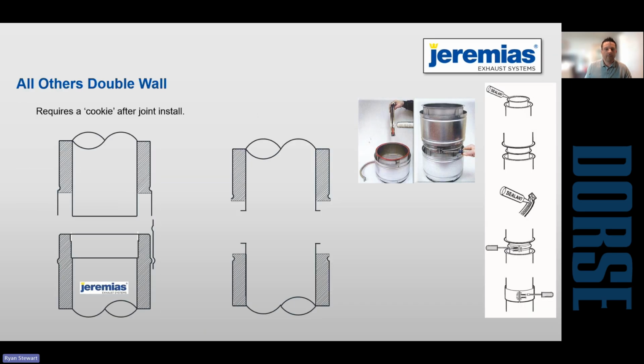What's unique about them compared to others, and they still build this as well, is there's a flange type product where you put a high temp sealant between the flanges, and then basically once you get that done, you put a clamp around the outside and a layer of insulation. Jeremias is the only one that offers a slip connection where the caulking goes on the outside of the duct. It slips in there and it's complete. So you don't have the extra insulation cookie that goes along there.